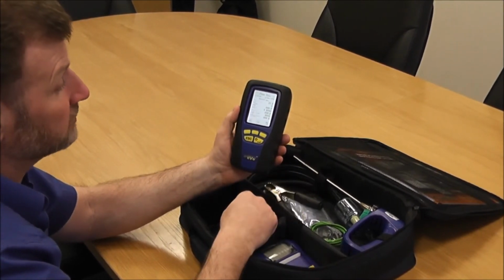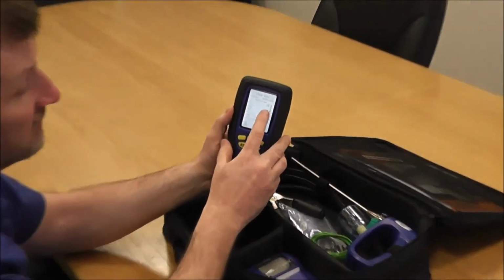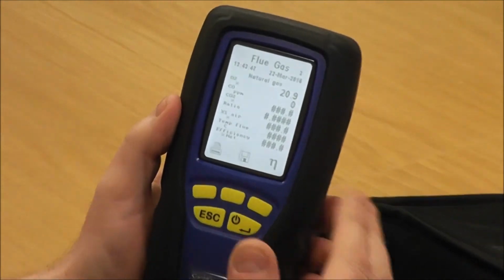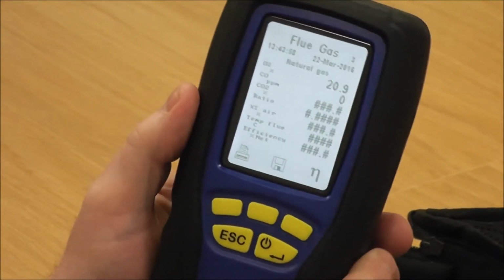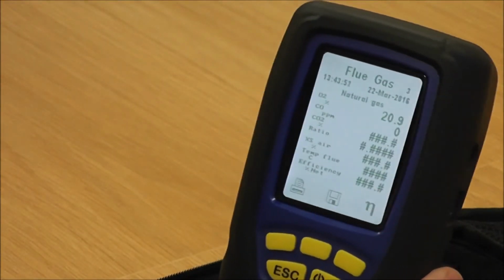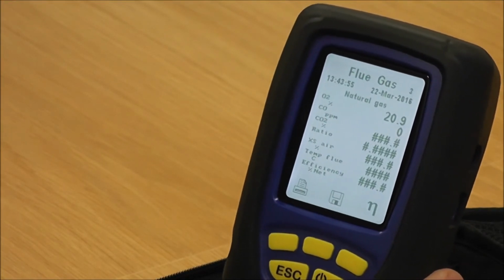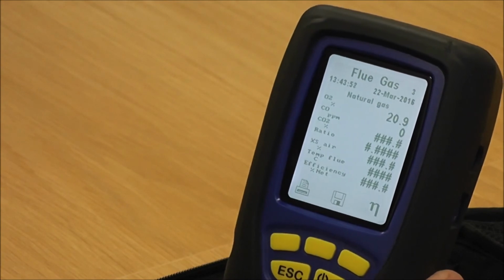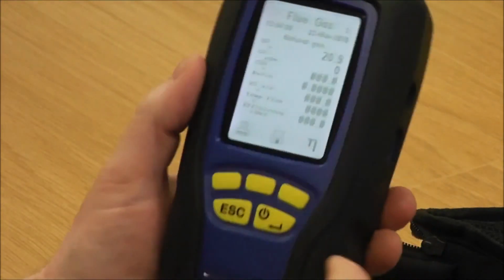Now unfortunately, there's no easy way of testing the CO like this. The only way you're going to be able to check the CO is actually on an appliance, but this is a good indication that everything is working okay and that your pump's all right and you don't have any internal tube issues. Thank you.